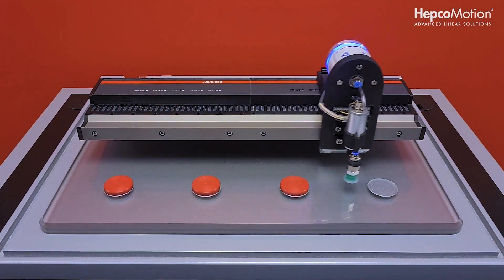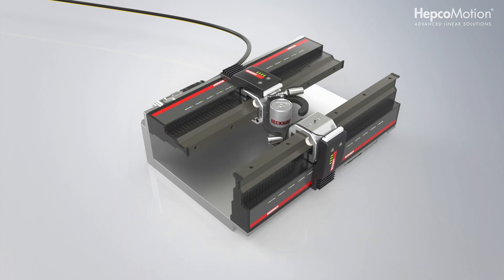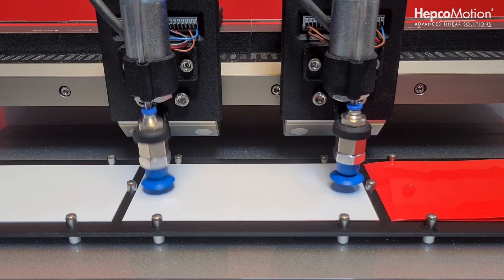What we can also do is add NCT — No Cable Technology — to the equation. NCT is essentially wireless induction power to the mover, providing up to three amps. The comms aspect is important because it allows you to do processing on the mover itself. The three amps will power actuators, suckers, and small servo motors, while the comms gives you the ability to control something and send data back to the controller. The signal is fully synchronous, operating within the EtherCAT world, which allows you to accurately process and track the progress of a product.